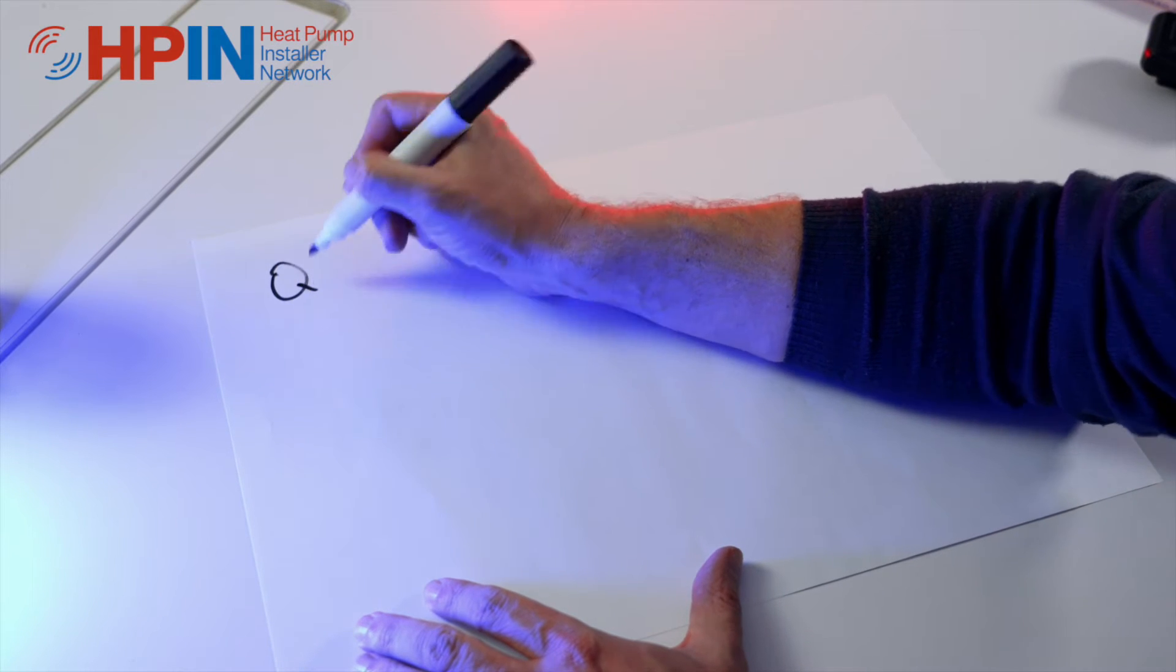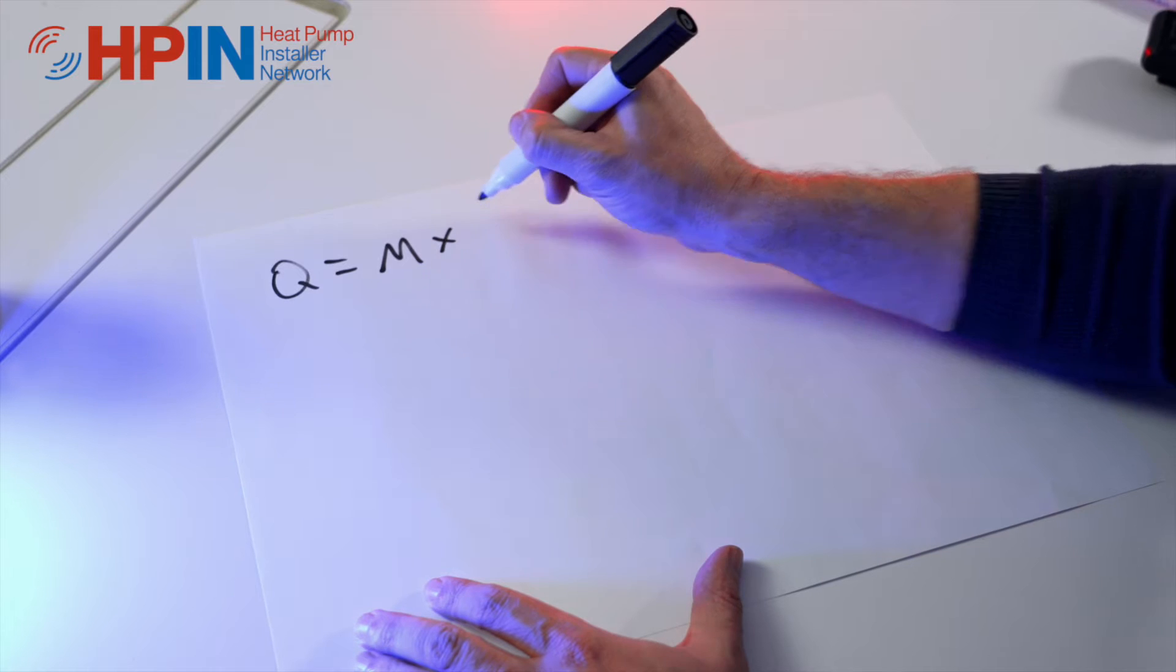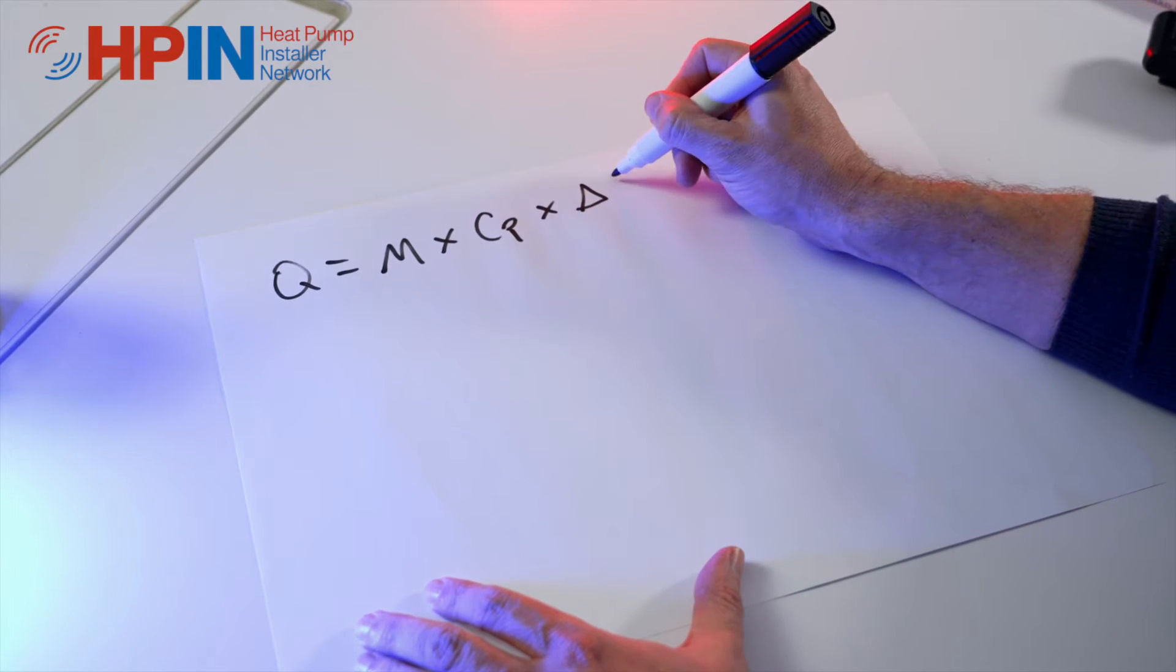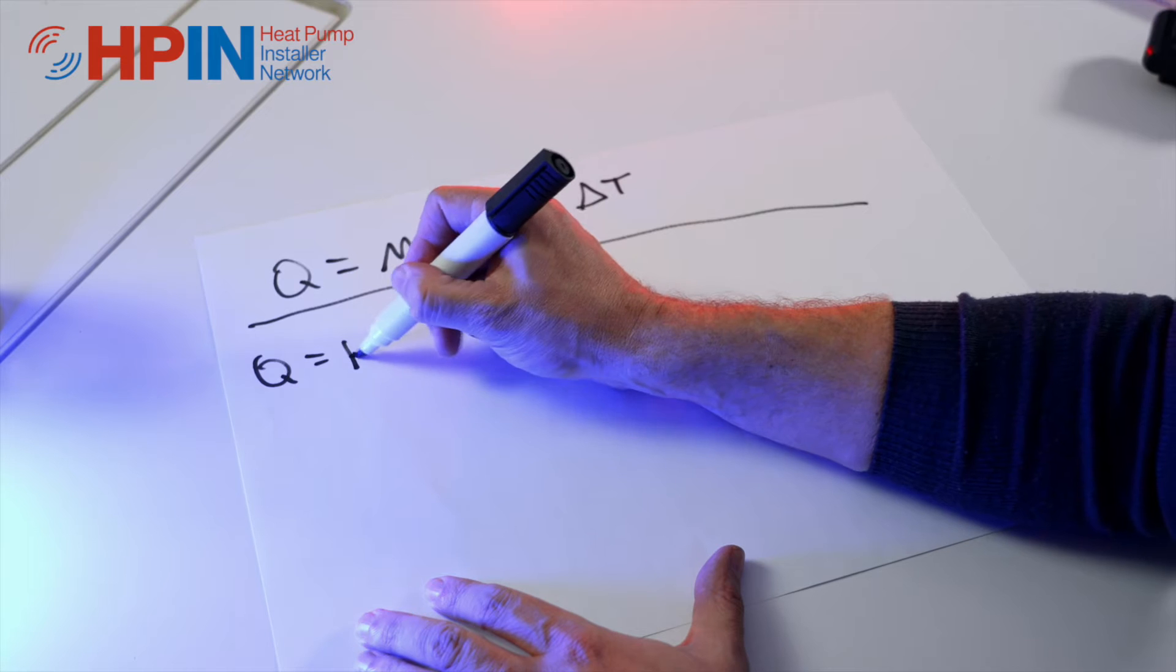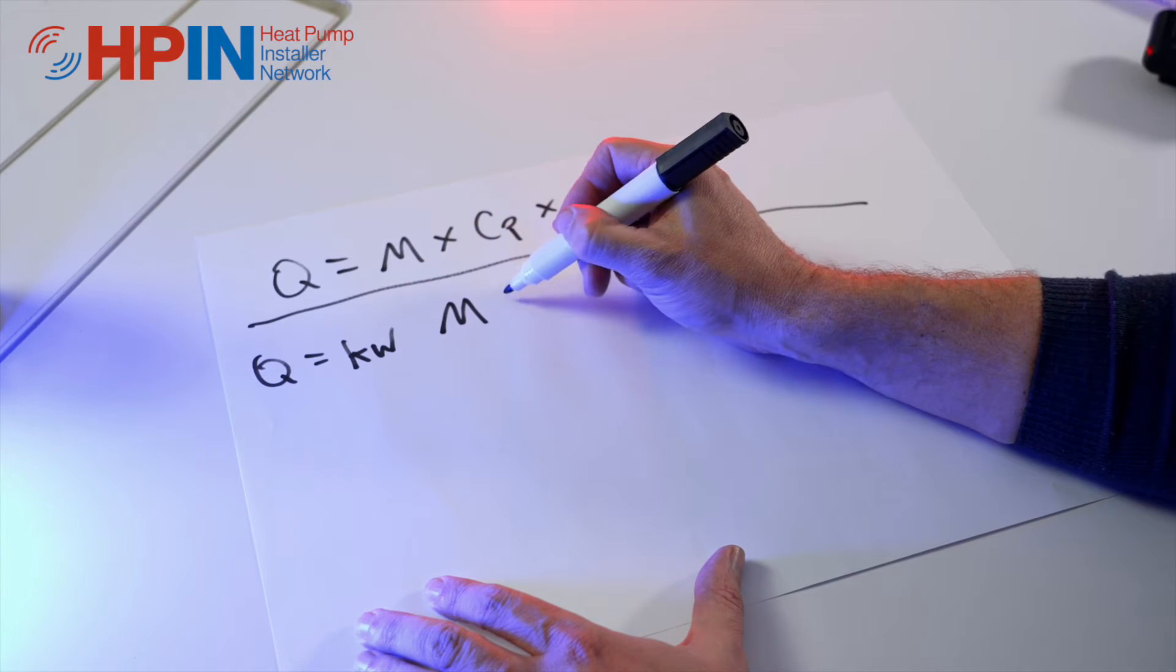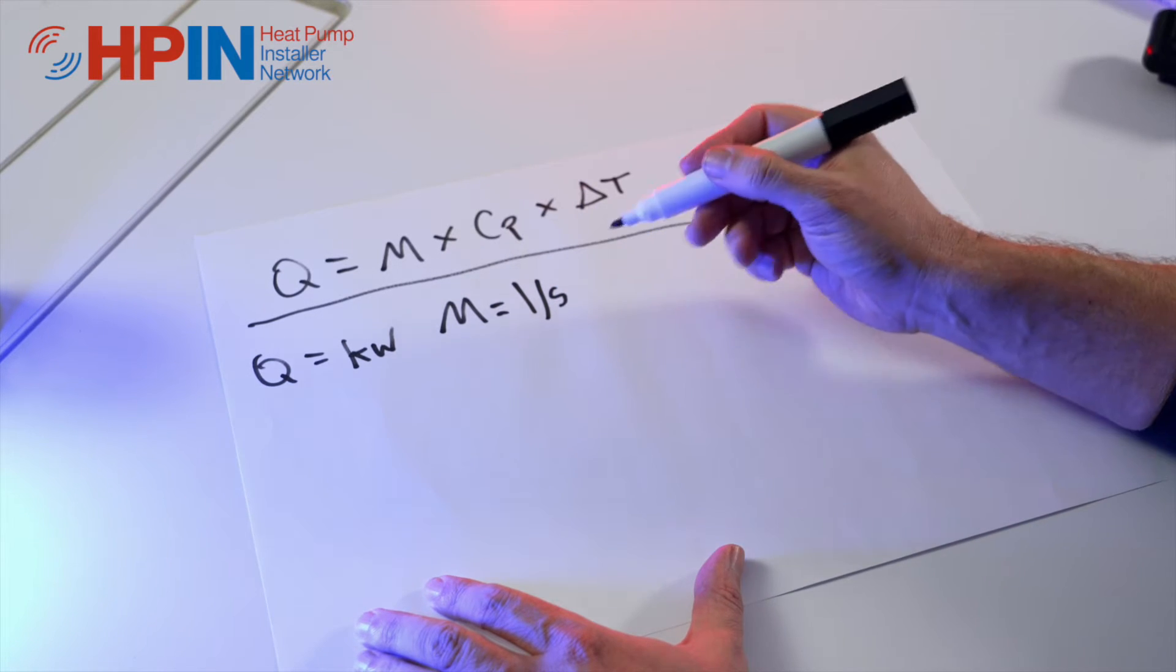We can use this equation to show how important flow rates can be. The equation goes like this: Q equals m times Cp times delta T. Q is our kilowatts, m is measured in litres per second, not litres per minute, so we'll have to convert that.